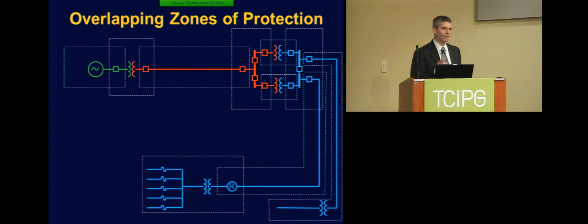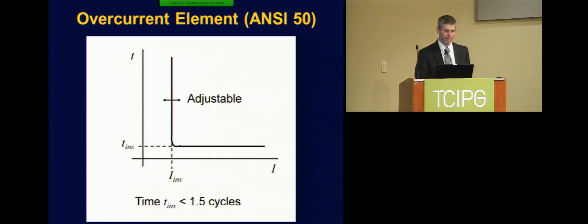This is a fun thing I like to remind people of. I've heard every once in a while that power engineers are Neanderthals, that they don't get high-tech stuff like layers of security. That's not true. Power guys understood overlapping zones of protection from day one. They've always built in security. In this picture, we have a generator on the left-hand side, where the box also includes the green square, which is a circuit breaker. Conversely, the transformer relay protects both of those circuit breakers. So the power industry is well versed in these overlapping zones, the concepts of layered security, redundancy, and backup protection. They're well in tune with the ideas of cybersecurity and what we do.